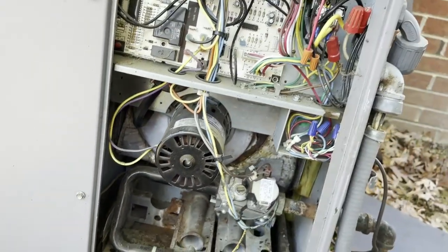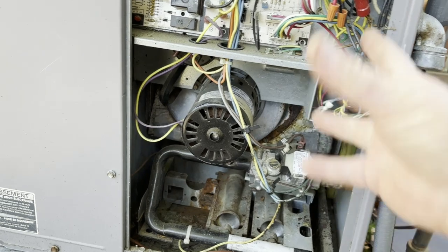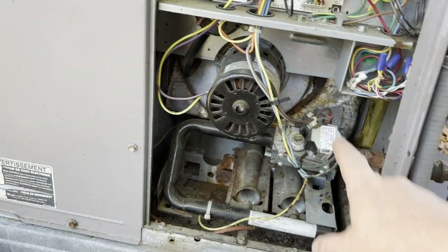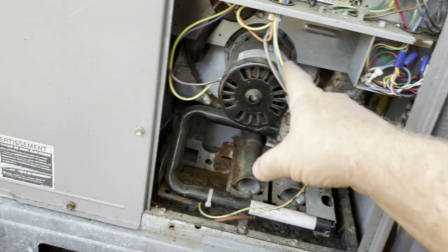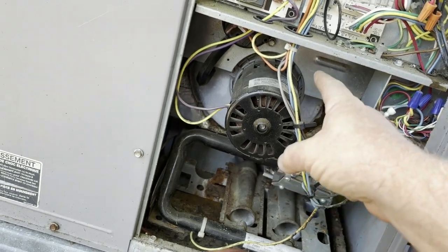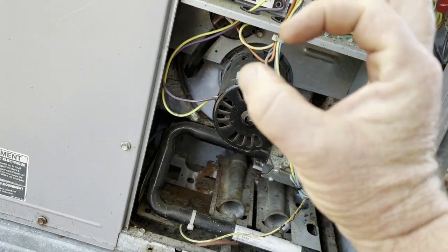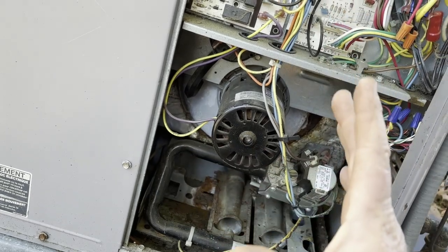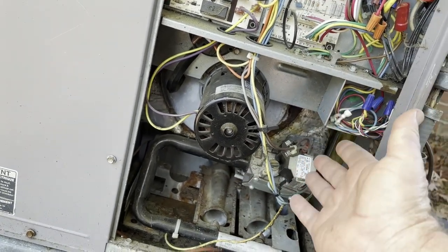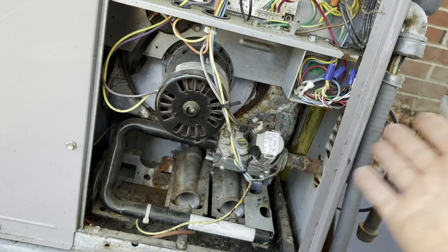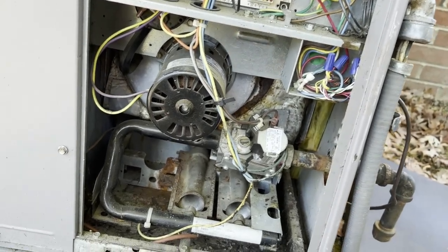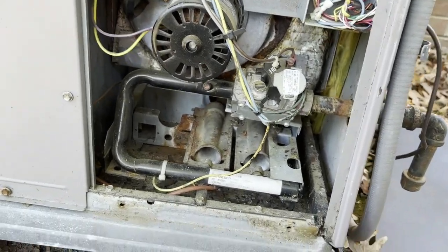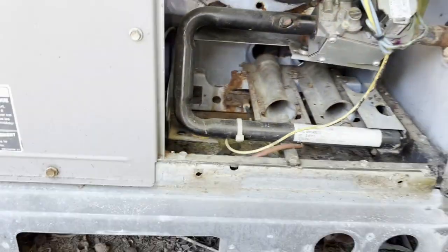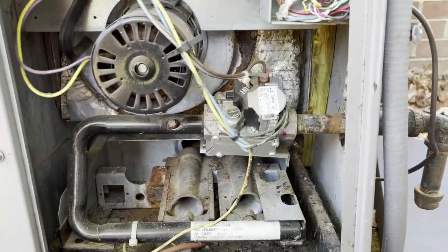Because what's going to happen is you're going to show up, get this apart, get it out, take that one off, and once you get the draft motor off, you're going to find the opening for that draft motor to be rusted apart. And then now you're going to call, and they're not going to have that faceplate in stock, and now you've got a unit torn apart and completely broken down, and now you got a part that you got to wait a week for.